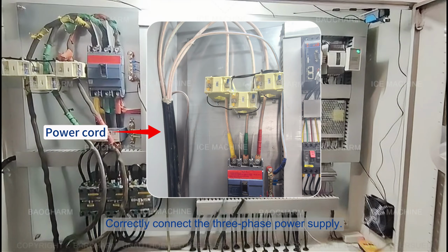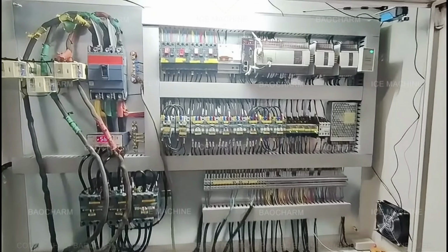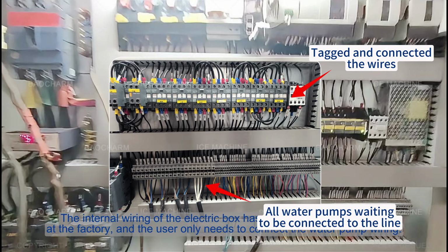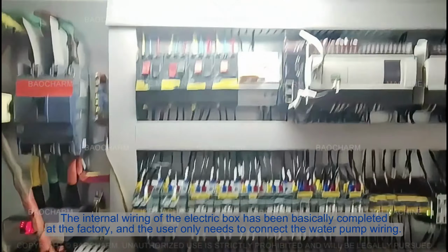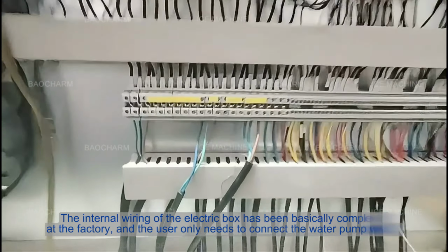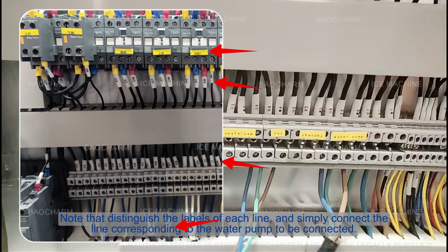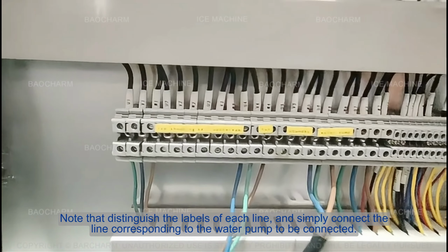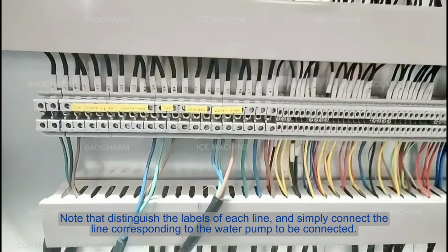Correctly connect the 3-phase power supply. The internal wiring of the electric box has been basically completed at the factory, and the user only needs to connect the water pump wiring. Note to distinguish the labels of each line, and simply connect the line corresponding to the water pump to be connected.